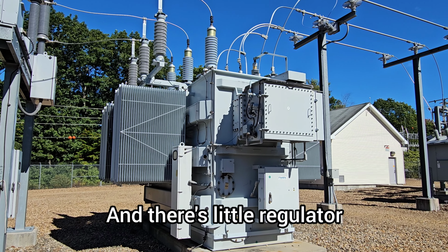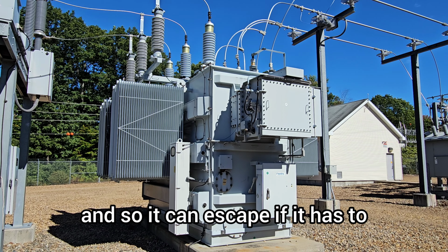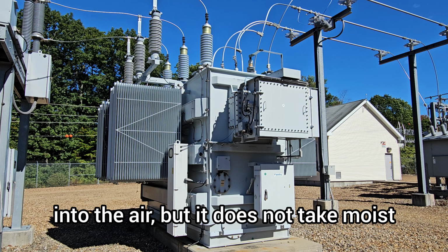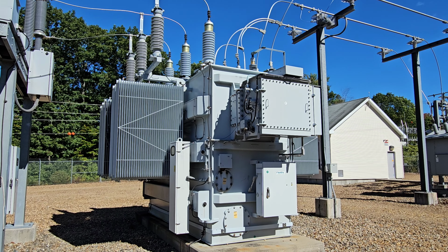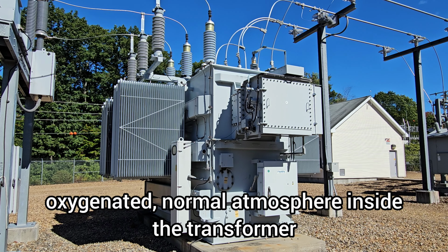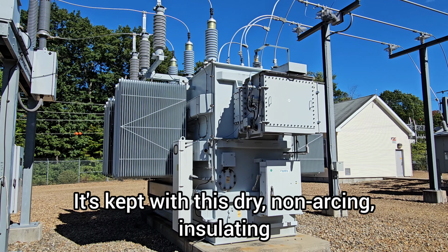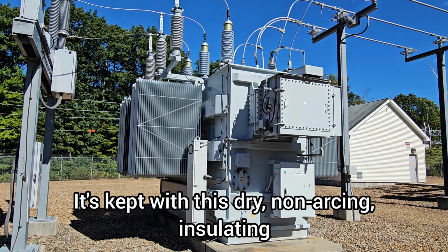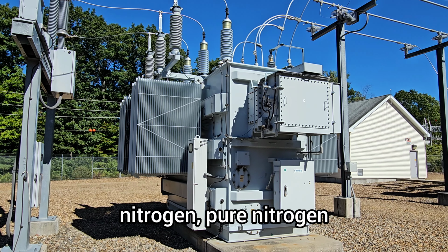There's a little regulator, so it can escape if it has to into the air, but it does not let in moist, oxygenated, normal atmosphere inside the transformer. It's kept with this dry, non-arcing, insulating nitrogen, pure nitrogen.